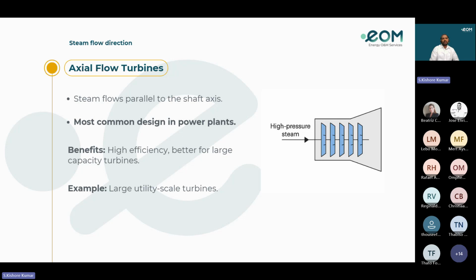Axial flow turbines. An axial flow turbine is a type of turbine where the working fluid, typically steam or gas, flows parallel to the axis of rotation of the turbine rotor. In this turbine, fluid enters and exits the turbine in the same general direction along the axis of the shaft. It is the most common design in power plants, and the benefits are high efficiency and suitability for larger capacity turbines. Examples are large utility scale turbines.